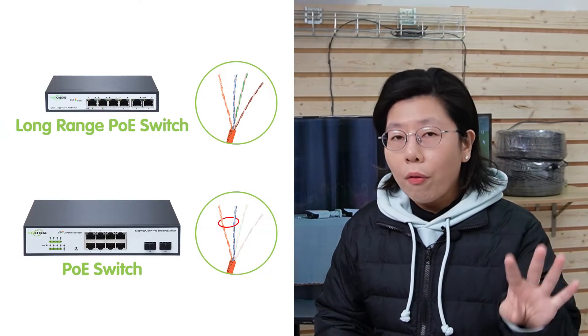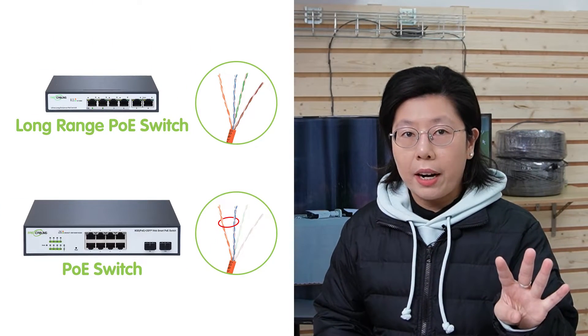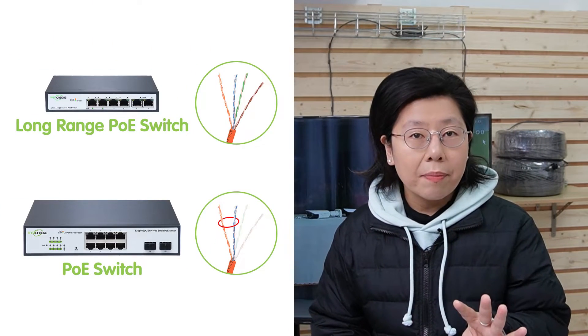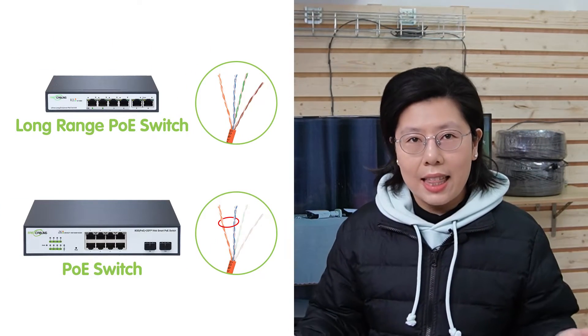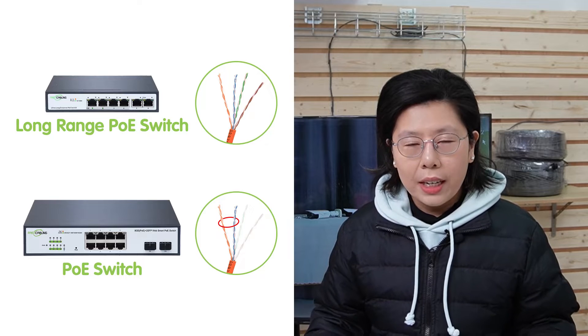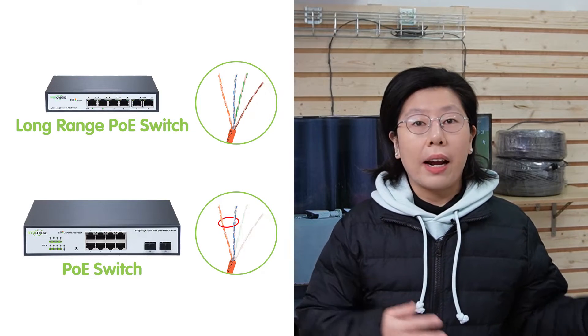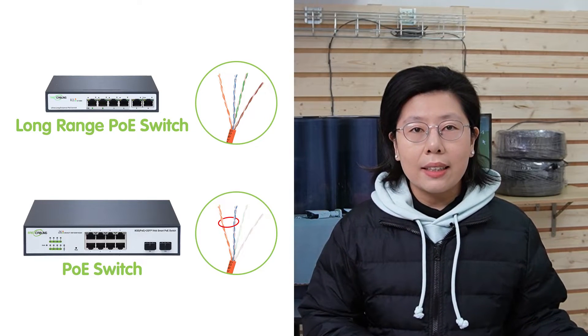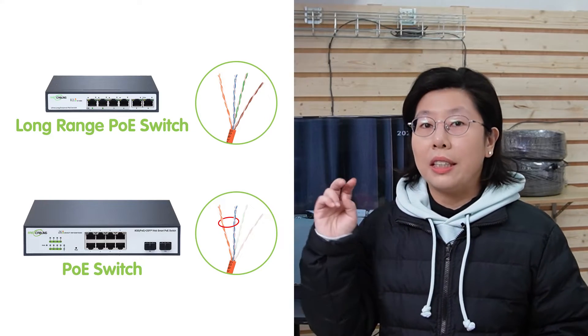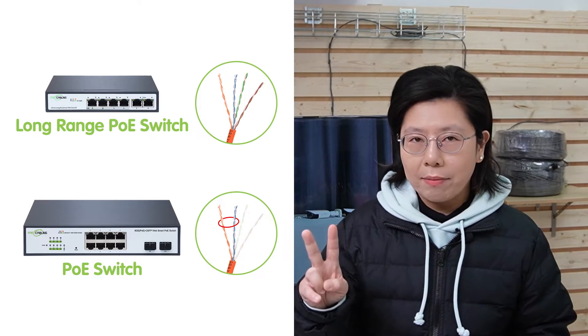Now the key to its effectiveness lies in its use of all four twisted pairs of the wire in an Ethernet cable, compared to regular POE that uses only two pairs. So this design can significantly improve the power transmission efficiency over longer distances and ensure that the PTZ camera can function reliably, even when it's located far from the power source.